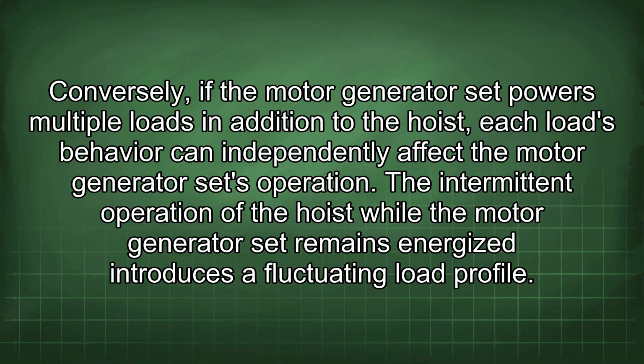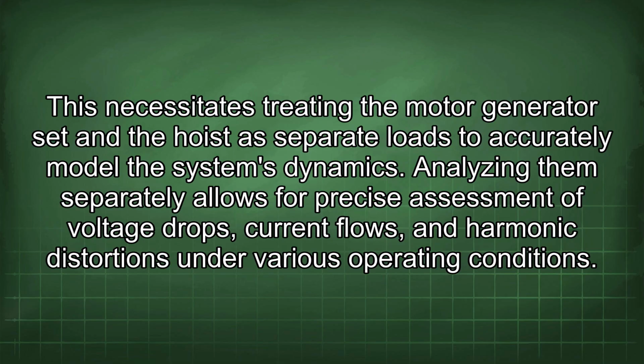Conversely, if the motor generator set powers multiple loads in addition to the hoist, each load's behavior can independently affect the motor generator set's operation. The intermittent operation of the hoist while the motor generator set remains energized introduces a fluctuating load profile. This necessitates treating the motor generator set and the hoist as separate loads to accurately model the system's dynamics. Analyzing them separately allows for precise assessment of voltage drops, current flows, and harmonic distortions under various operating conditions.